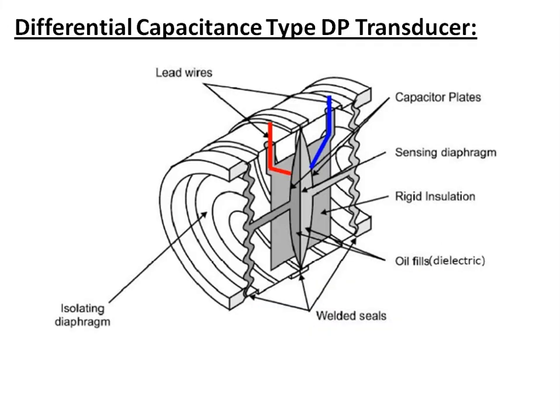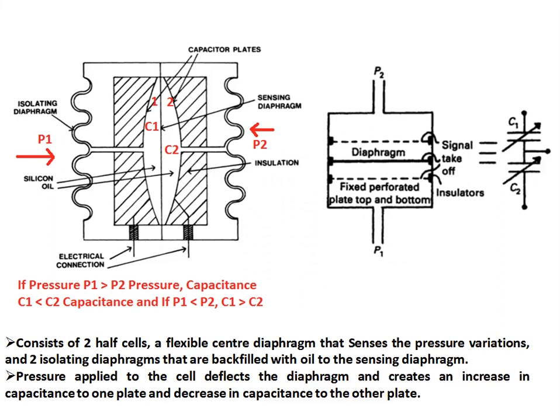To overcome the disadvantage of single-ended capacitors, a differential capacitor type DP transducer is used. In this DP transducer there are three plates: one moving plate — the sensing diaphragm — at the center, and two fixed plates on either side of the sensing diaphragm. P1 is the pressure applied to one side of the DP transmitter through an isolating diaphragm, and P2 is the pressure applied to the other side.